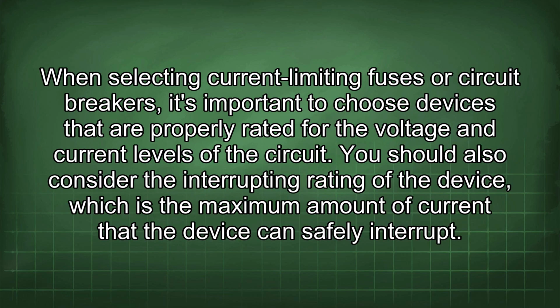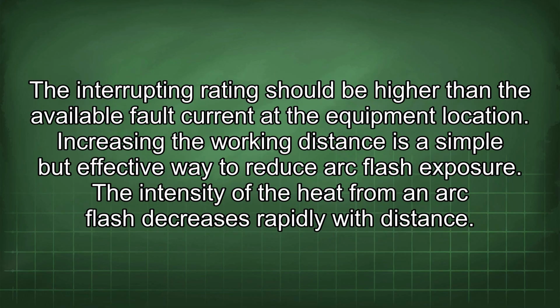When selecting current-limiting fuses or circuit breakers, it's important to choose devices that are properly rated for the voltage and current levels of the circuit. You should also consider the interrupting rating of the device, which is the maximum amount of current that the device can safely interrupt. The interrupting rating should be higher than the available fault current at the equipment location.